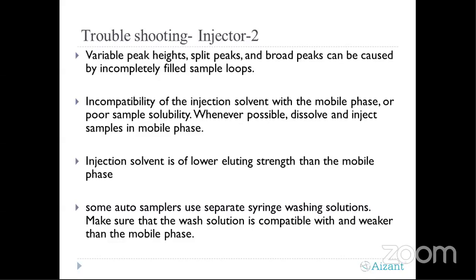The second point is a part that comes from the development of the method. If during development it is not taken care of, the compatibility of the diluent system which we use for sample preparation versus the mobile phase, and there is a huge difference between the polarity of your mobile phase and injection solvent, you will not get a symmetrical Gaussian peak. You will get a distorted peak, and baseline drifts will always be challenging.